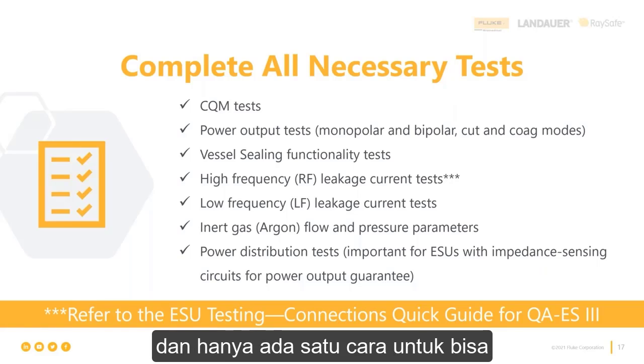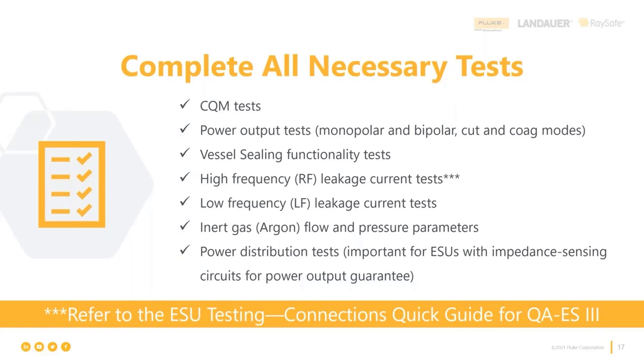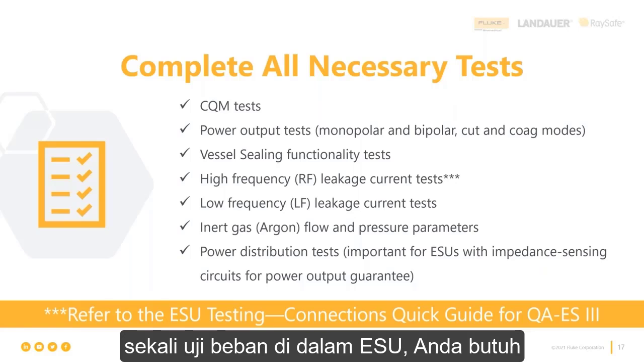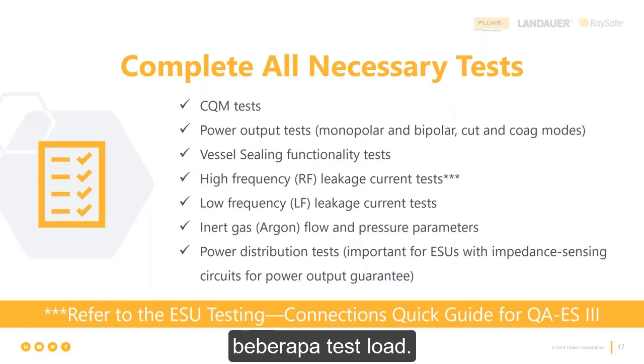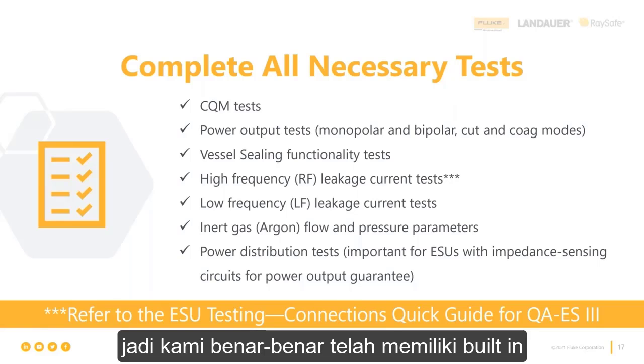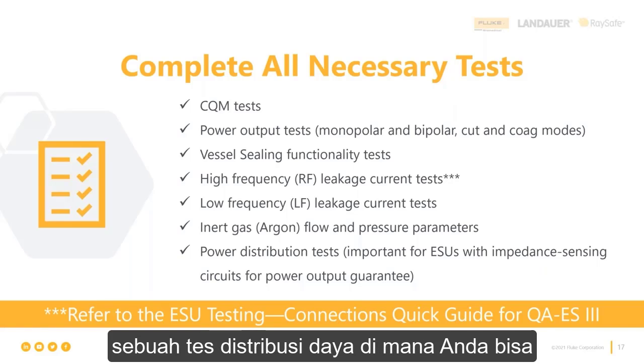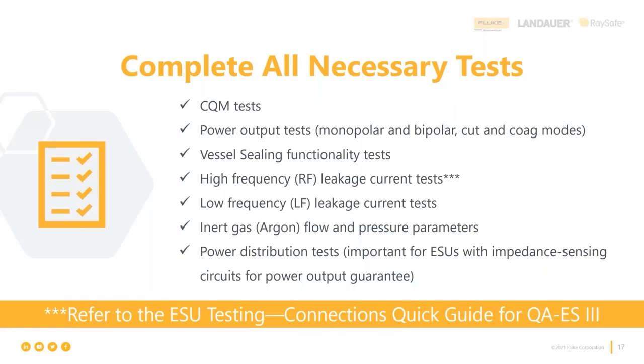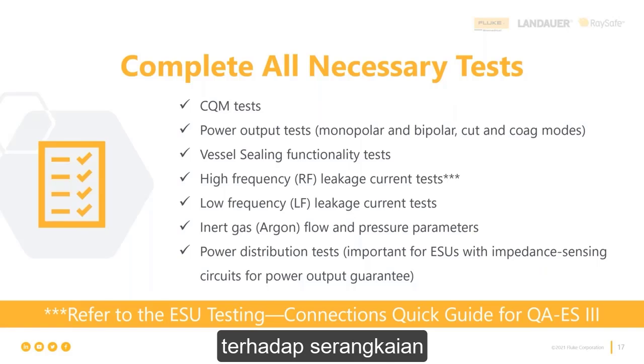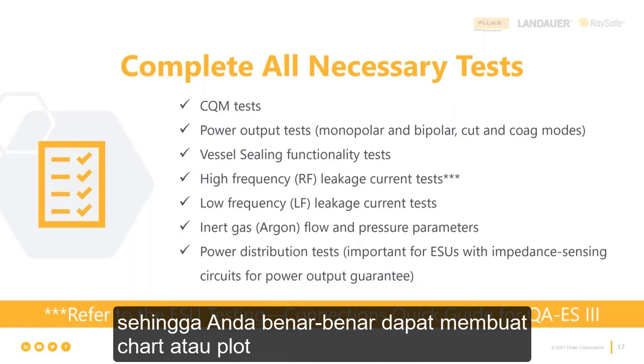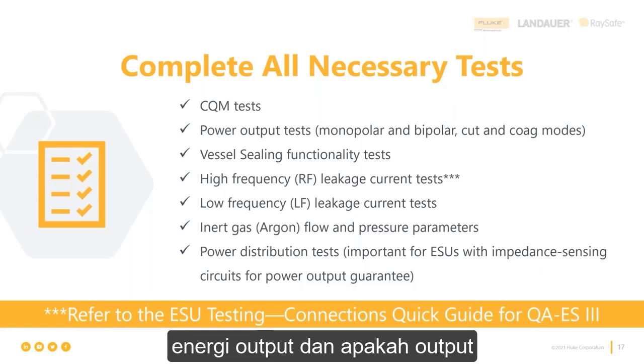And there's only one way to be able to do these tests. You can't do it with just a single test load inside the ESU. You need multiple test loads. And so we have actually built in for a long time a power distribution test where you can set up the maximum output energy setting on the ESU, and you can run it against a series of selected patient load impedances or resistances. So you can actually chart or plot the output energy and whether the output energy guarantee functionality of the ESU is working right.